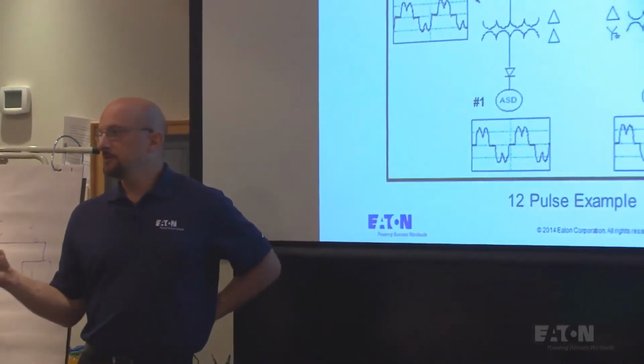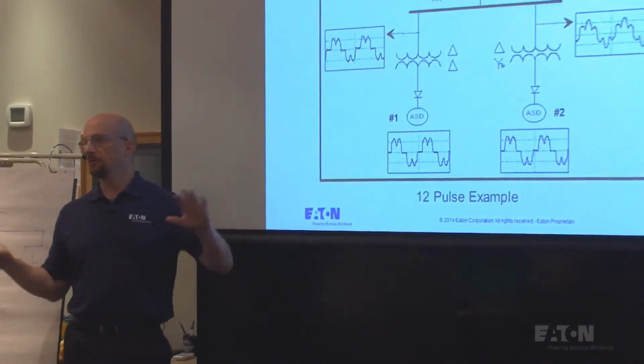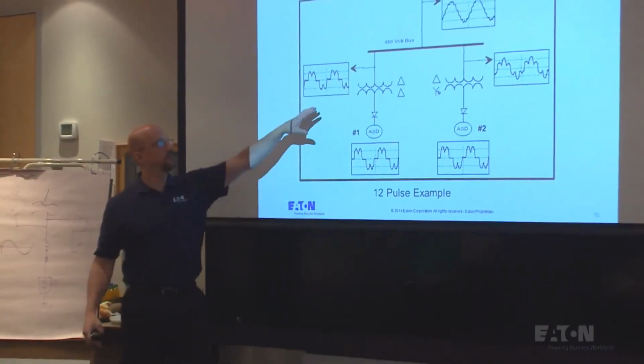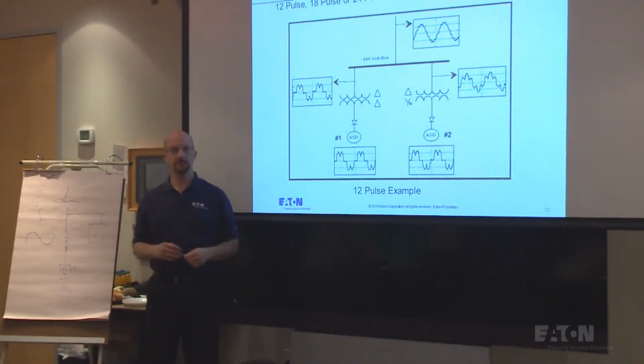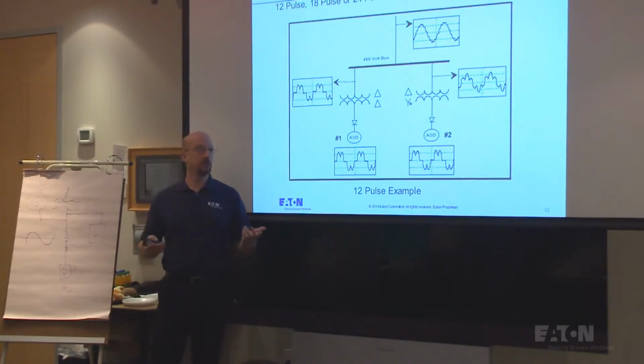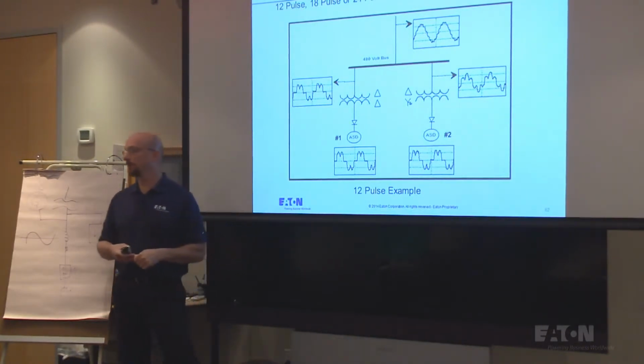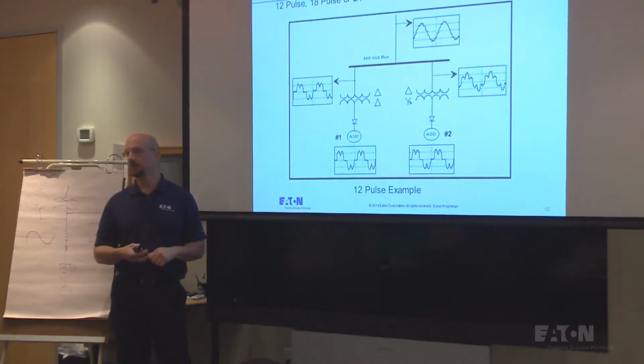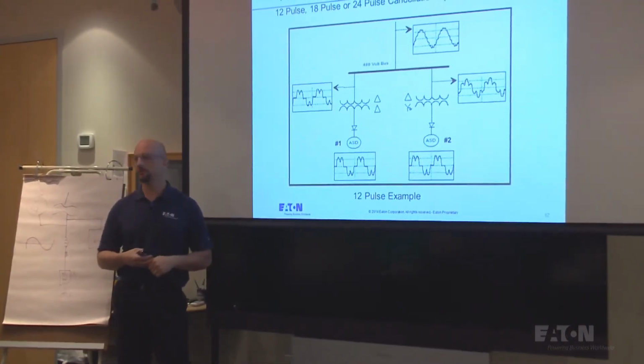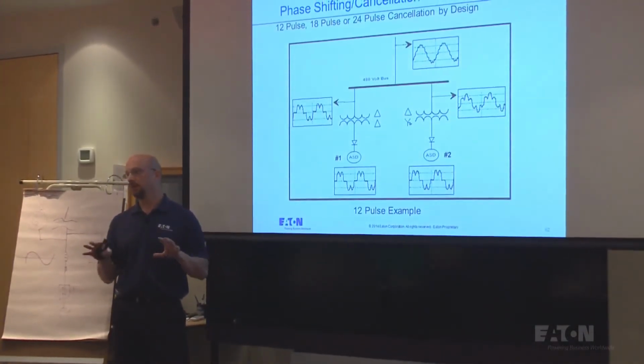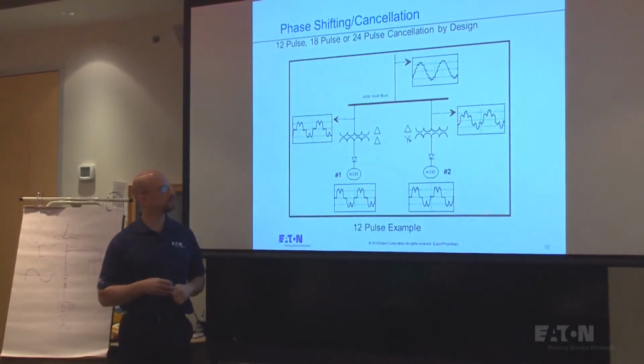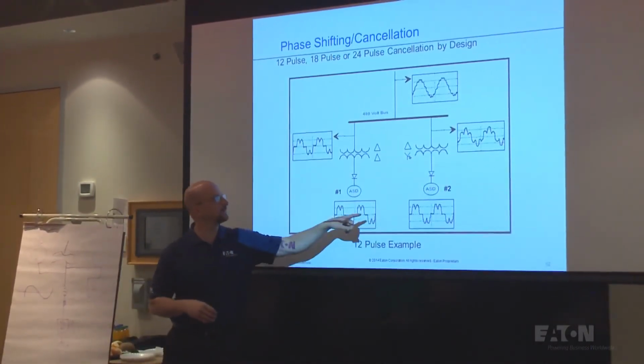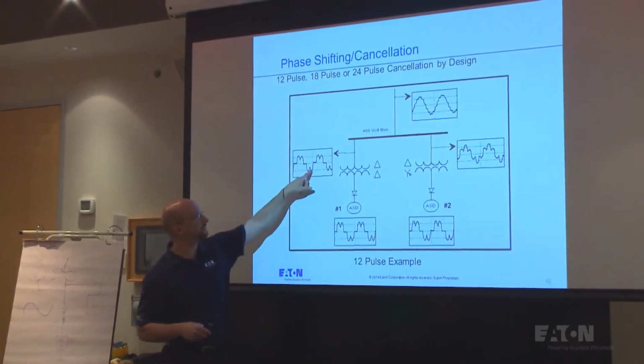Has anybody ever used phase shifting to cancel harmonics? You take two transformers and you put a delta delta and a delta Y, and you end up phase shifting. Yeah, it's a very good way to get rid of harmonics, because now you don't have to worry about that overcompensation with harmonic filters. And a lot of times you need transformers anyway, either to step down, or maybe you're using drive isolation transformers. So you take two currents that look like that, you combine them. This one doesn't get shifted.